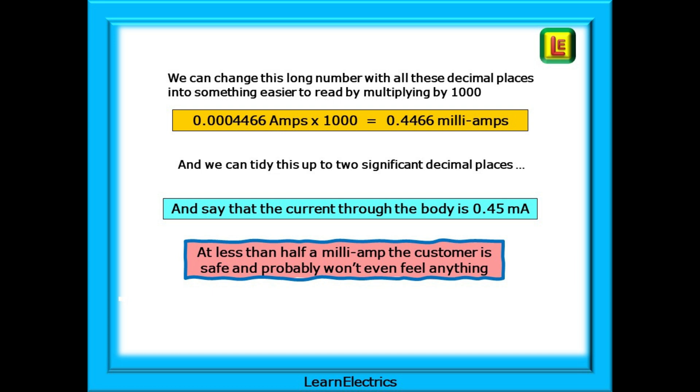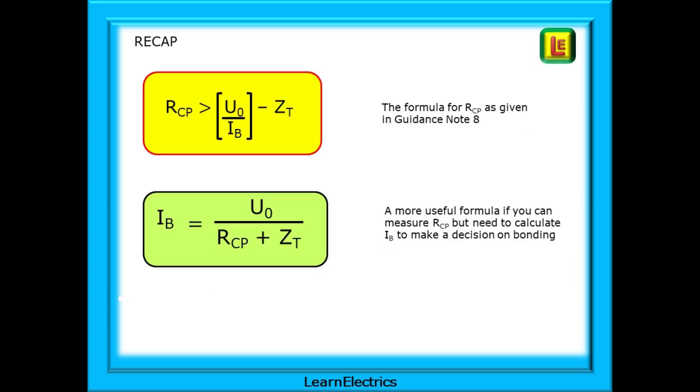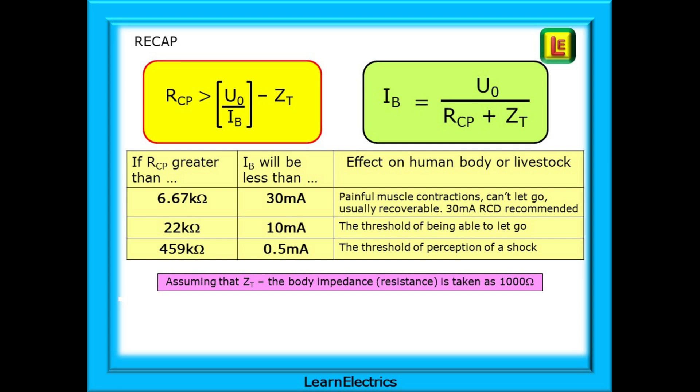A quick recap on the two formulas that we used. RCP can be found by dividing the nominal voltage by the desired maximum fault current through the body, and then subtracting the impedance of the body, which is often taken as 1000 ohms. We rearranged this formula to arrive at a second one that would give us the current flowing through a human body if we already know the resistance to the conductive part. This was achieved by dividing the voltage by the sum of the measured resistance and the impedance of the body. Now we can calculate either the minimum resistance, RCP, or we can calculate the maximum current, IB. This table gives a reminder of these resistances and currents and their effect on the human body or livestock.